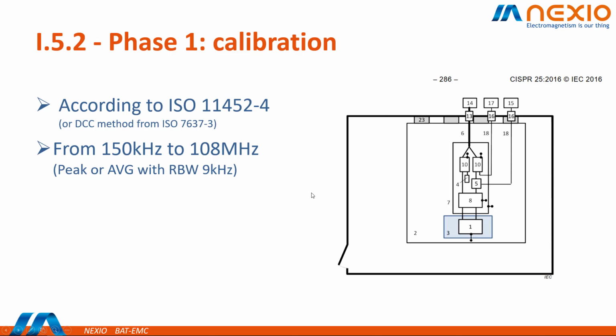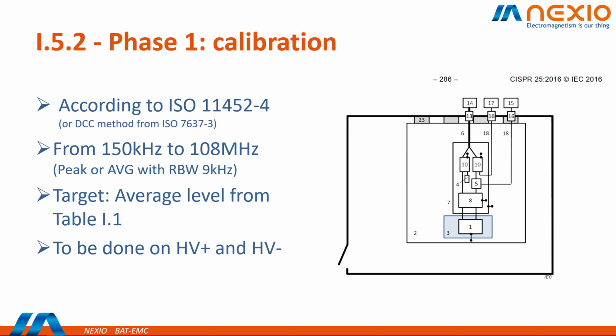This describes the range from 150 kHz to 108 MHz, peak or average, with the RBW of 9 kHz. We use the average level from the table I1 as the target, and it's to be done both on the plus and minus sides of the high voltage lines. In orange, you can see the injection path. Blue, you can see the measurement path. And there you have it for the calibration.